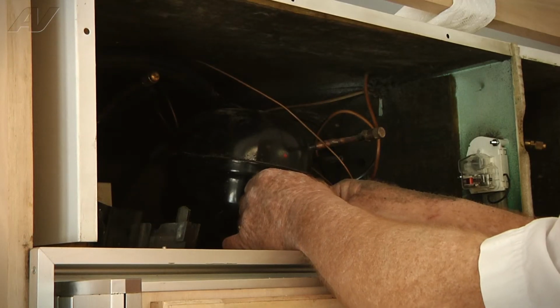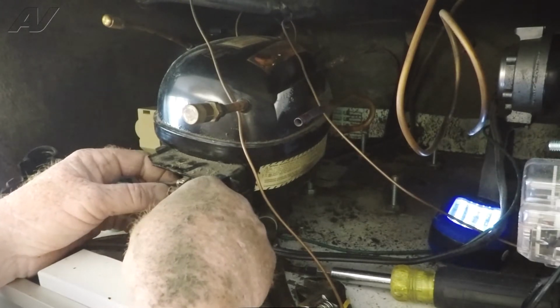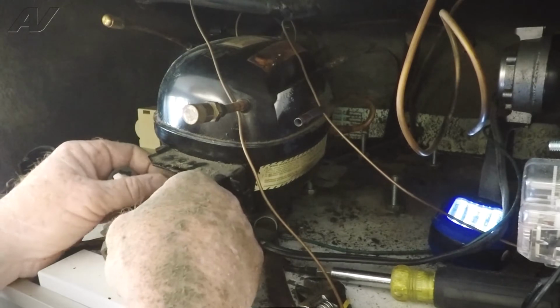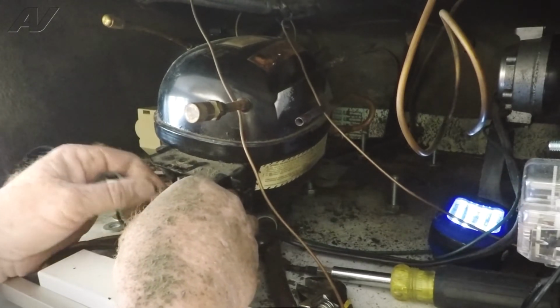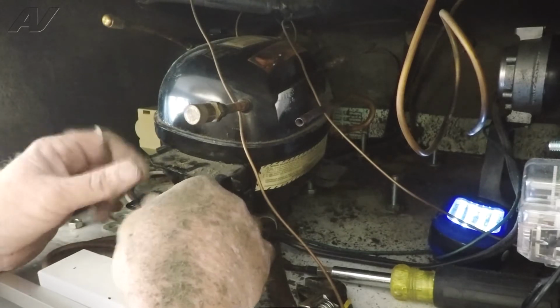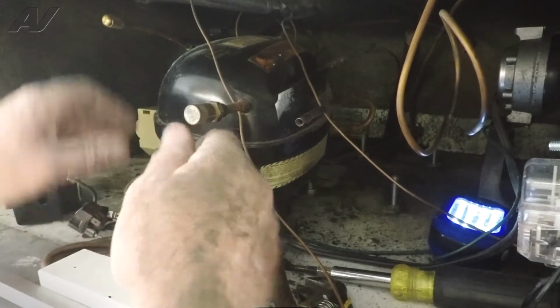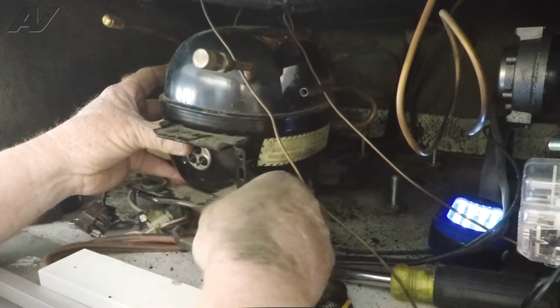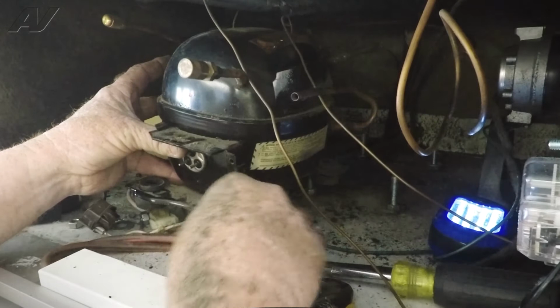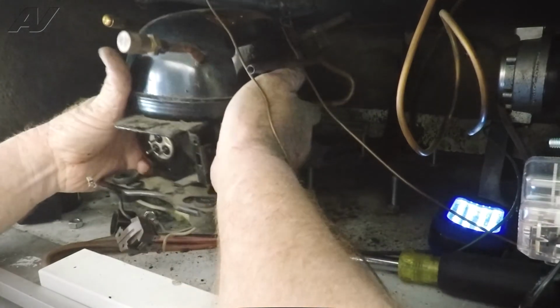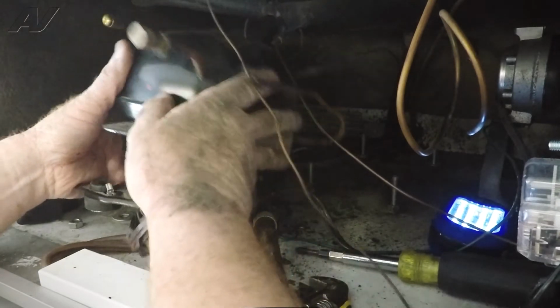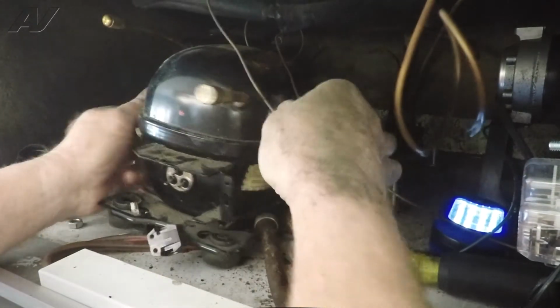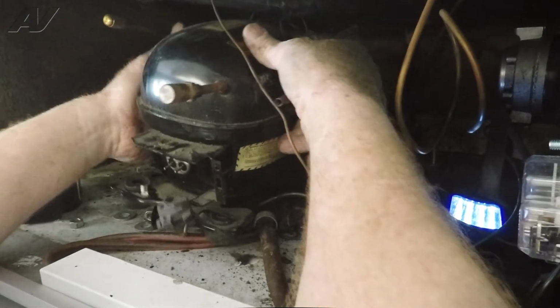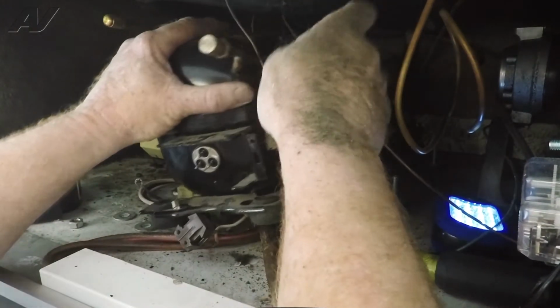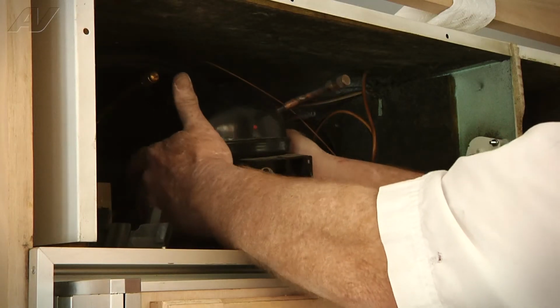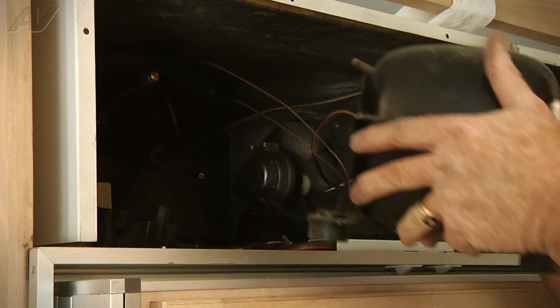Before removing the compressor, you want to remove the start components off the compressor, which would be the relay and the wire terminal from the thermal cutout, and just let them lay there. And now we'll raise the compressor up enough to get over the wiring and slide it, to make sure your cap tube doesn't get caught on that high side line on the compressor. Slide it all the way out and set it aside.